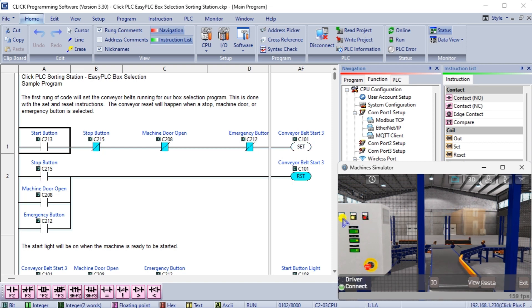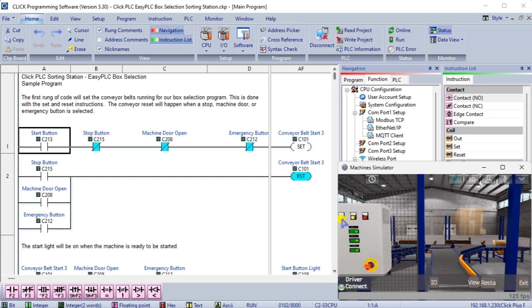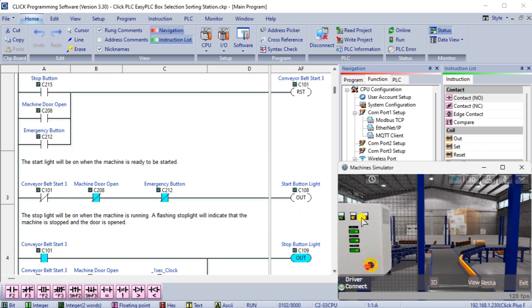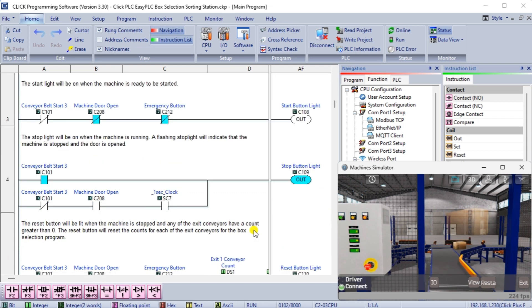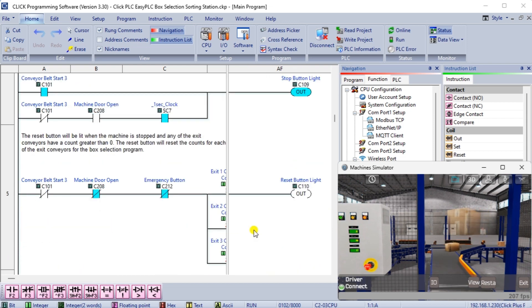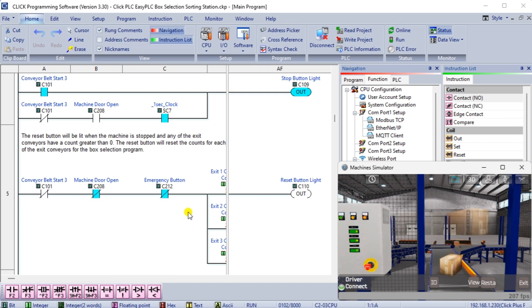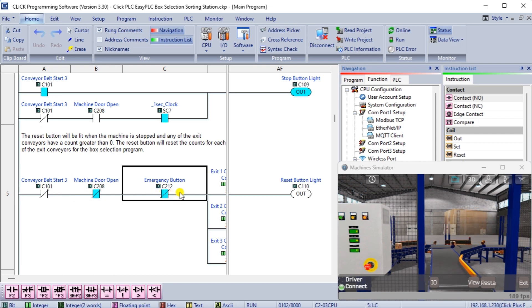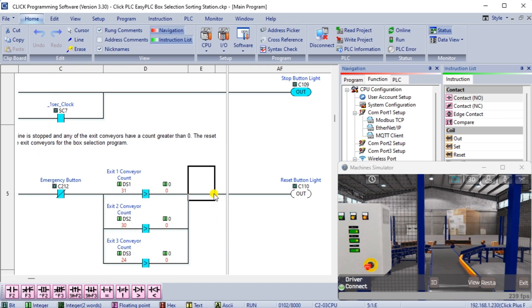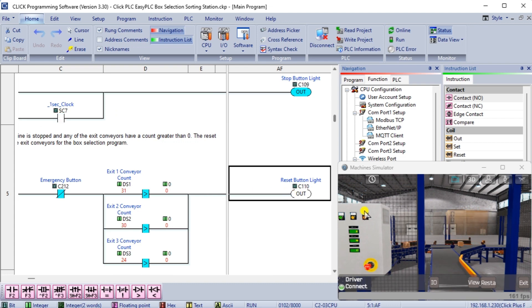The conveyor reset will happen when a stop, machine door or emergency button is selected. The start light will be on when the machine is ready. The stop light will be on when the machine is running. A flashing stop light will indicate that the door is open to the machine. The reset button will be lit when the machine is stopped and any exit conveyor having a greater than zero count. The reset button will reset the counts for each exit conveyor for the box selection program.